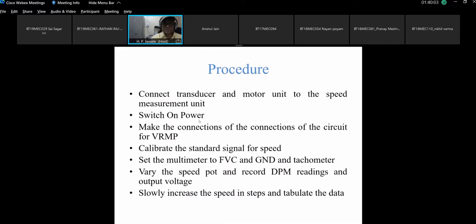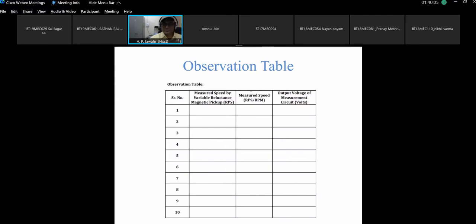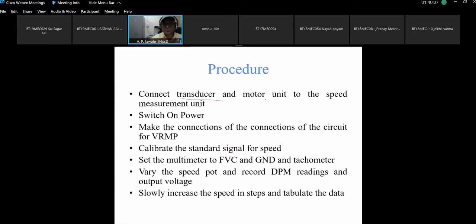Connect the transducer and the motor unit to the speed measurement unit, switch on the power, make the connection of the circuit for variable reluctance magnetic pickup, calibrate the standard signal for the speed. First of all, we need to calibrate. Now for calibration, what we do at 0 speed, we see that 0 signals are achieved, that the display panel is going to show 0.